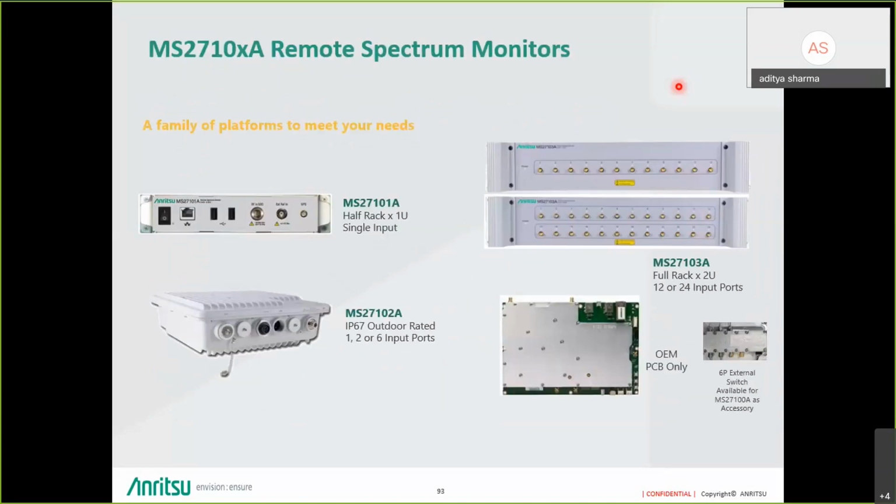Then Spectrum Monitor is there. Spectrum Monitor is for a customer who is looking for 24 hours into 7 into 365 days of monitoring, so they can adopt it for that. These instruments are there to run all day long without any problem.